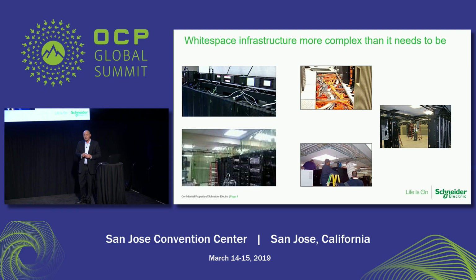Moving to a raised floor environment, what initially starts out as a very well-designed, well-organized layout of fiber, copper, and power quickly becomes messy and complicated. As you make adds, moves, and changes, you're moving fiber, copper, and power cables to meet new demand wherever it is. And if you're cooling your data center by pushing air through the bottom of the raised floor, these changes can complicate things by blocking airflow and so on.